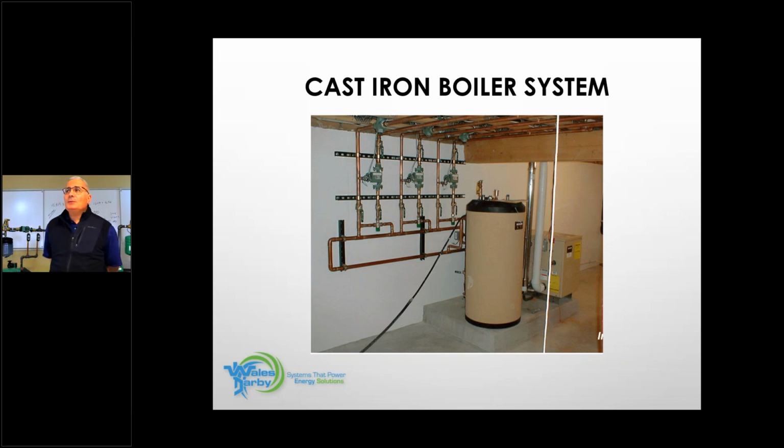Does he really need 3 water temperatures here on this job? Probably not. Even if it's a basement with 2 stories and I did all 3 levels, more than likely if you zone it right, you're down to 2 water temperatures. And I can even add mixing valves today that have outdoor reset built into them. That's the Taco iValve. So we can make the system even better. We can do that, okay?